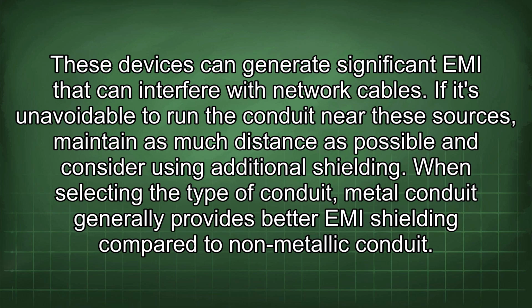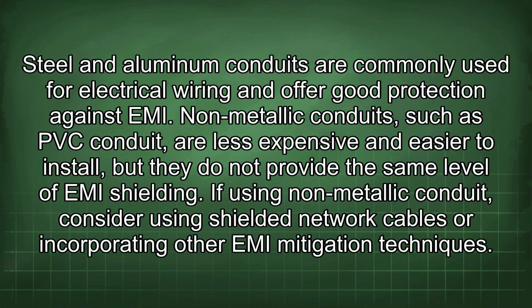shielding. When selecting the type of conduit, metal conduit generally provides better EMI shielding compared to non-metallic conduit. Steel and aluminum conduits are commonly used for electrical wiring and offer good protection against EMI. Non-metallic conduits, such as PVC conduit, are less expensive and easier to install, but they do not provide the same level of EMI shielding. If using non-metallic conduit, consider using shielded network cables or incorporating other EMI mitigation techniques.